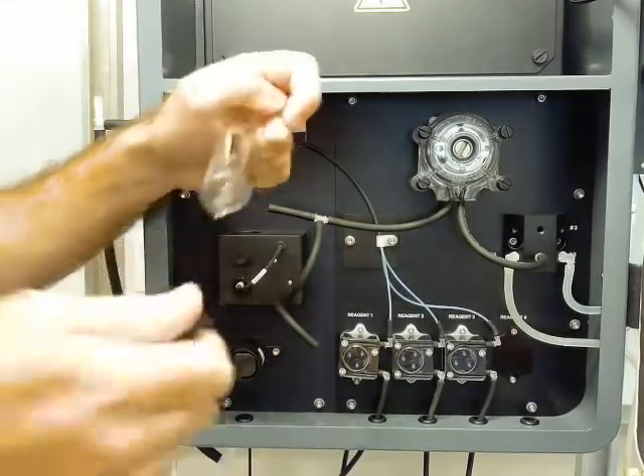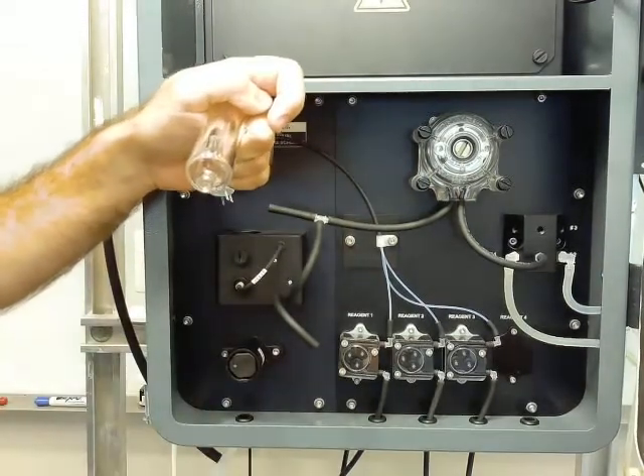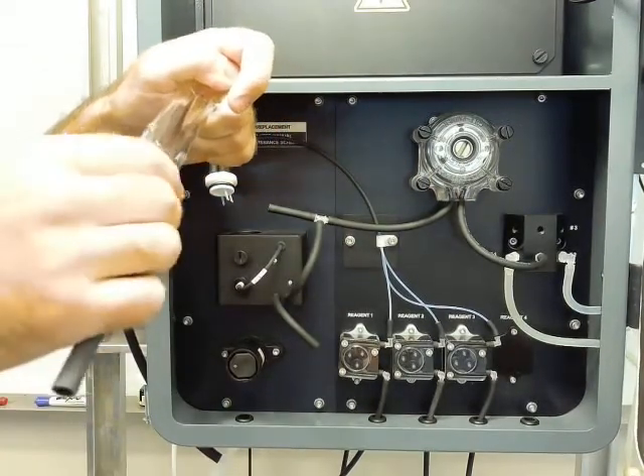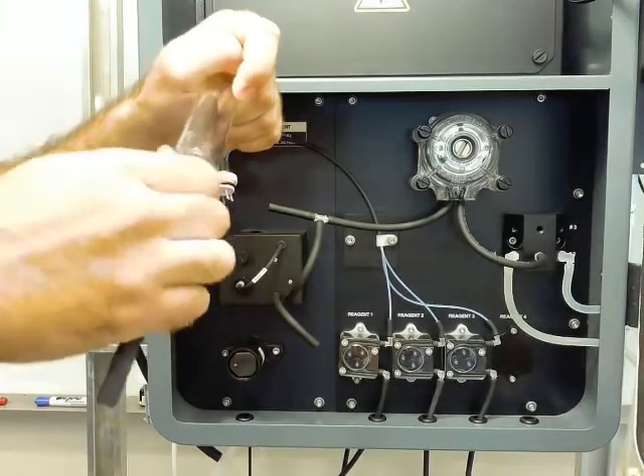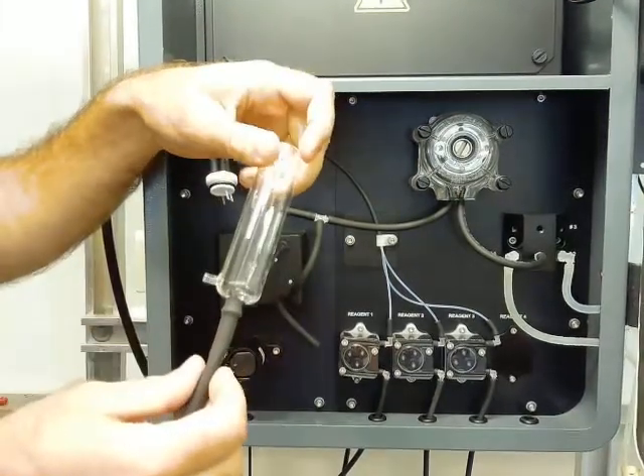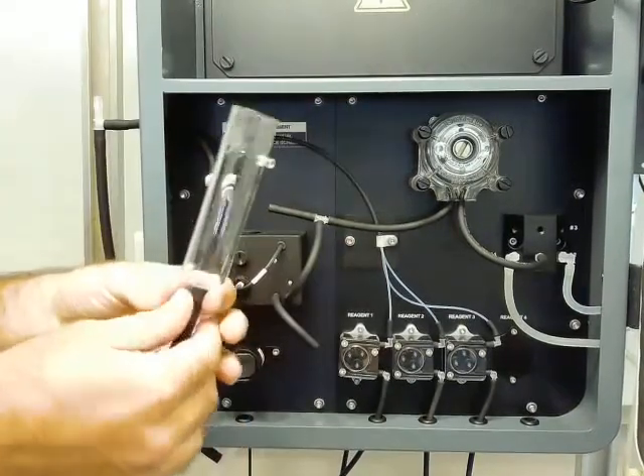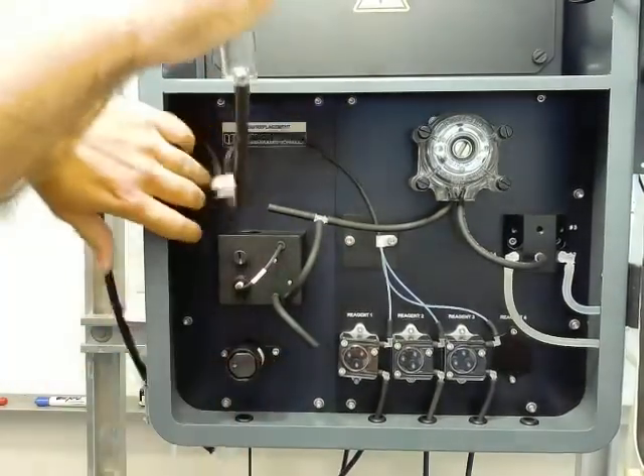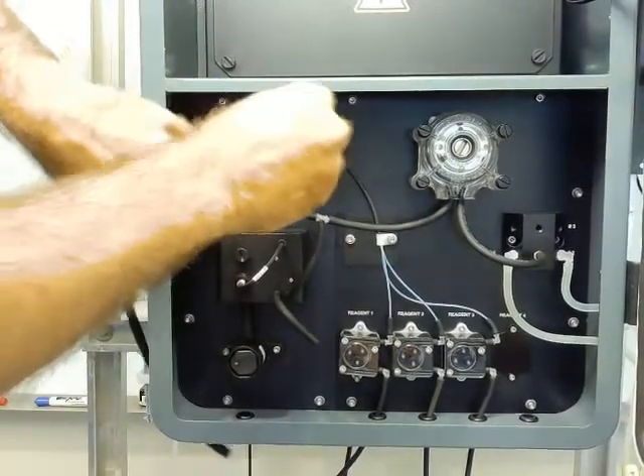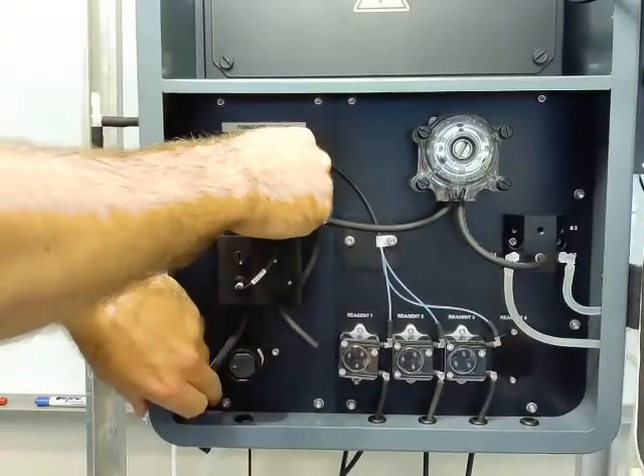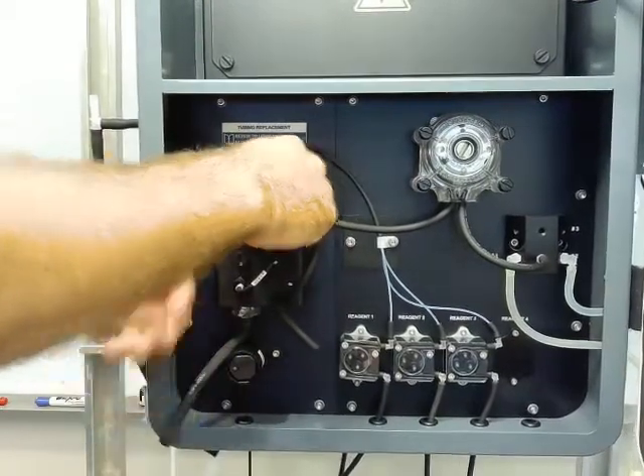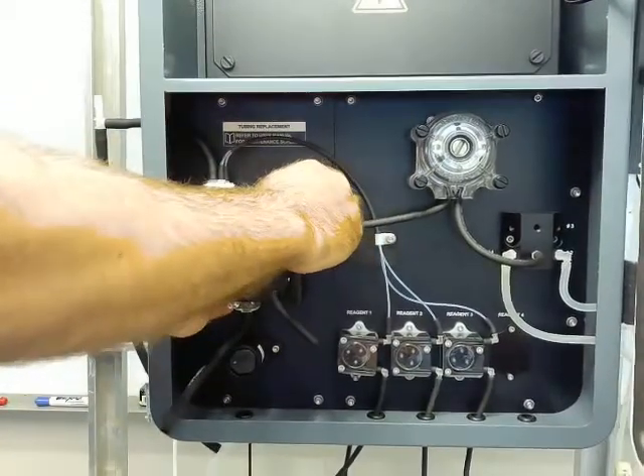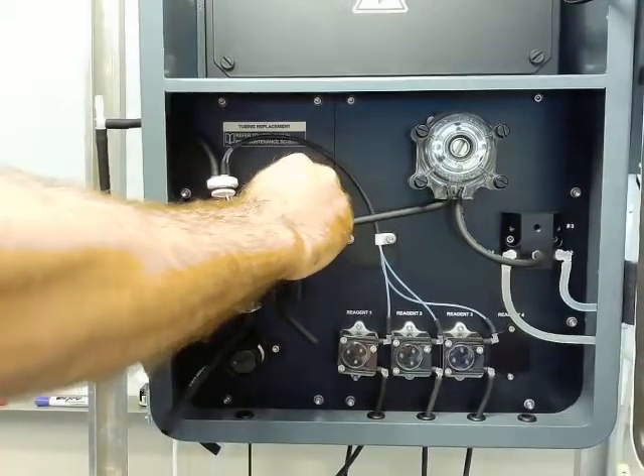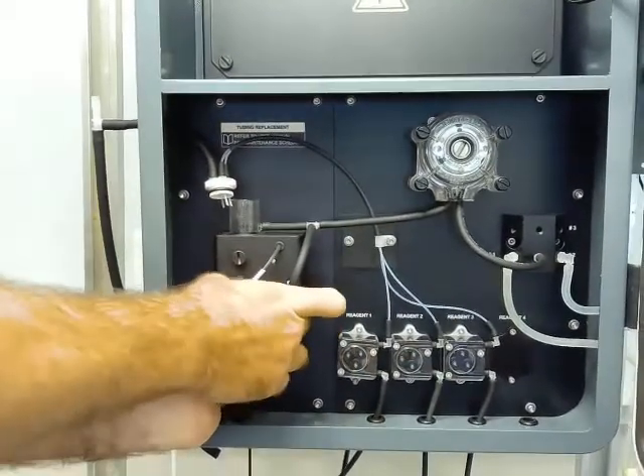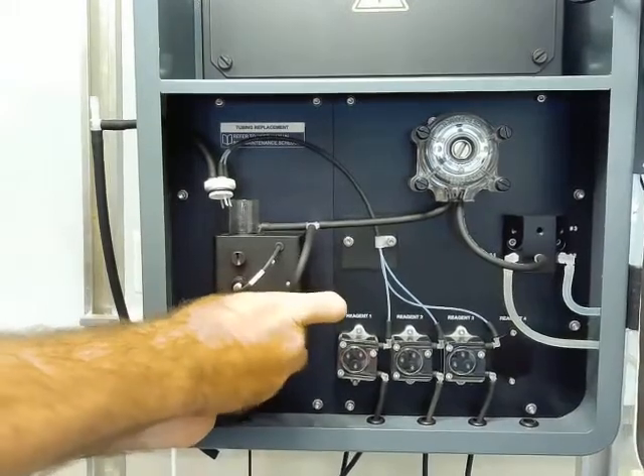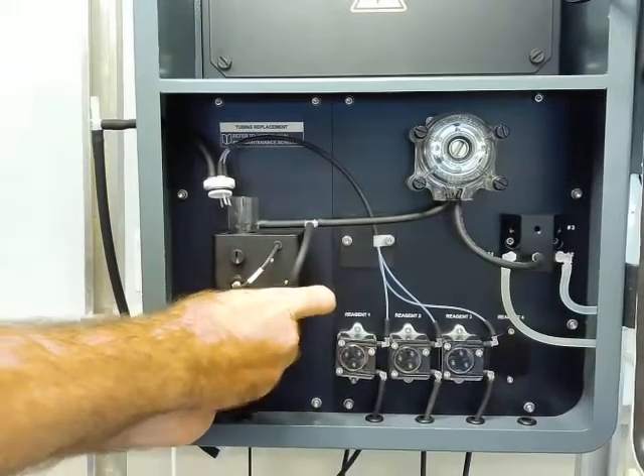Then actually just take the tubing off, just twist it off, grab the new one that should be cut to about the right length out of the kit, and twist that back into place. And again, wipe our cell one more time if we got any fingerprints on it, and then we can slide it back in place. Again, this is probably the most likely time that you break one of the inlet and outlets on it. The first thing I usually do when putting it back in is attach these mixing loop tubes just to give us a little cushion on those pieces should they bang against the flow cell block.